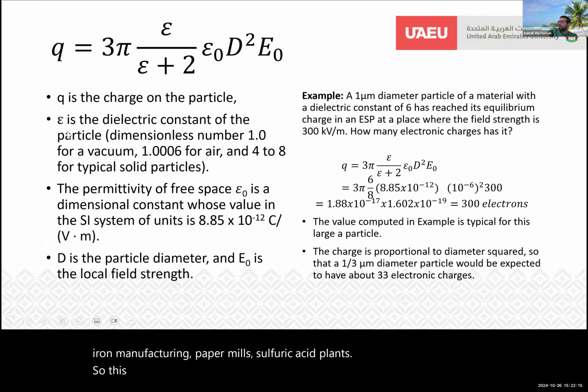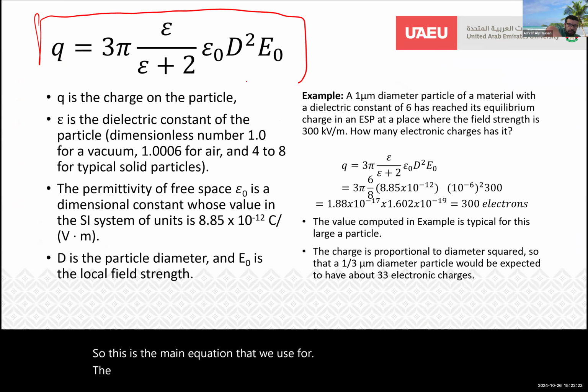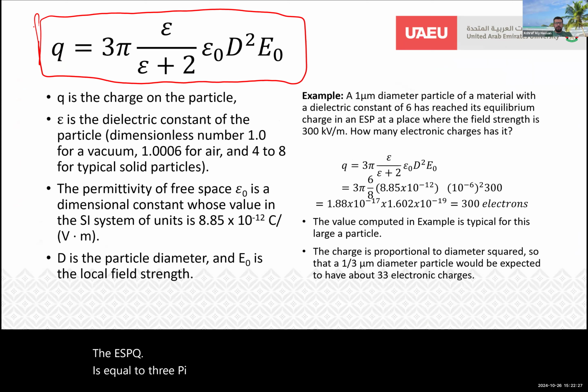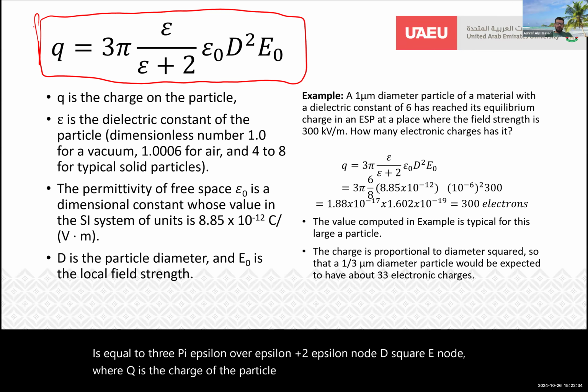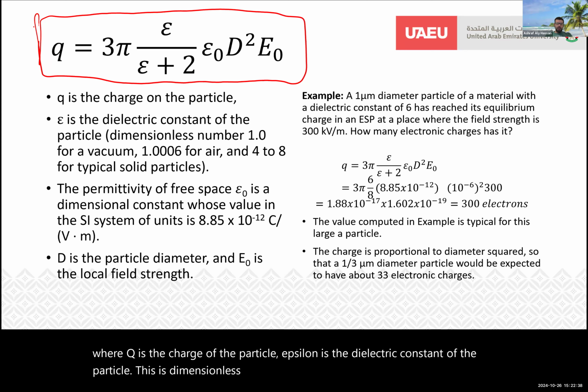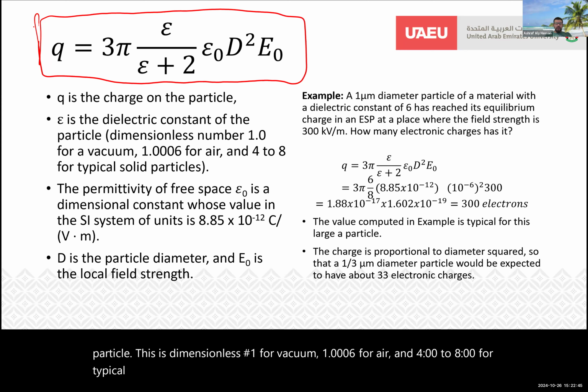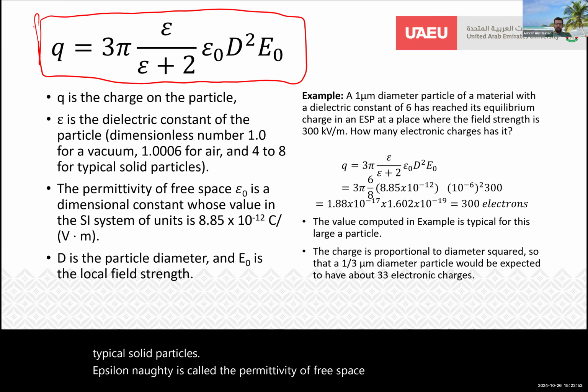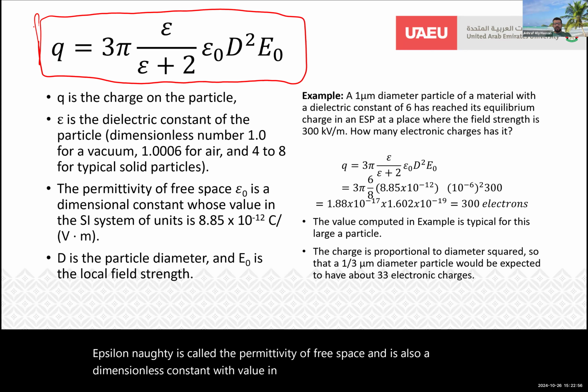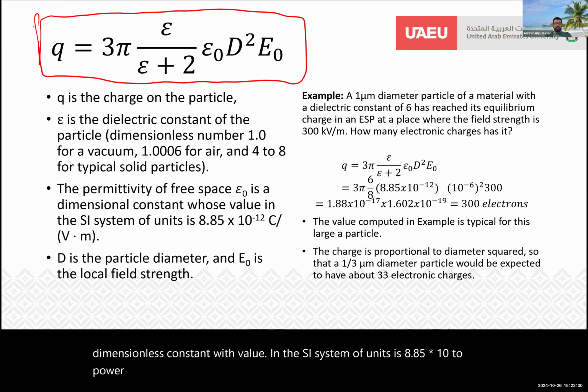So this is the main equation that we use for the ESP. Q is equal to 3 pi epsilon over epsilon plus 2, epsilon naught d square E naught, where Q is the charge of the particle, epsilon is the dielectric constant of the particle. This is a dimensionless number, 1 for vacuum, 1.0006 for air, and 4 to 8 for typical solid particles. Epsilon naught is called the permittivity of free space, and its value in the SI system of units is 8.85 times 10 to the power negative 12 coulomb per volt meter. D is the particle diameter, and E naught is the local field strength.